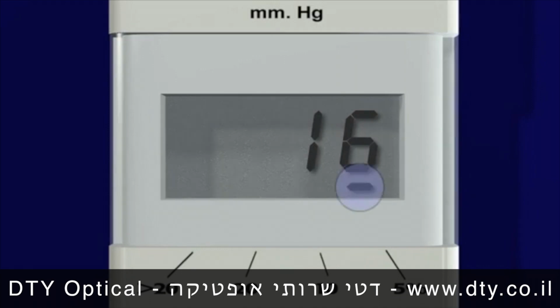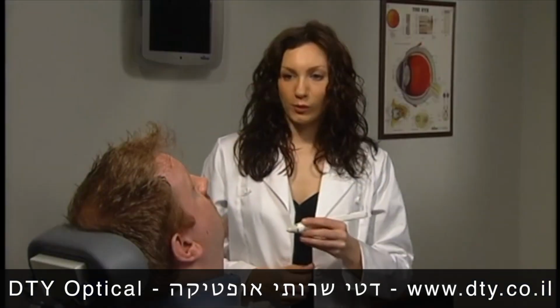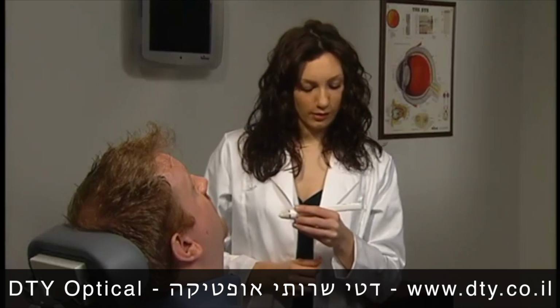Notice also the horizontal bar at the bottom of the LCD. This bar corresponds directly to the deviation index numbers. If the bar is situated at the far right of the screen, that means a deviation index of 5%. And if it's to the far left of the screen, that means a deviation of greater than 20%. Remember, the lower the number, the more reliable the reading. If you're satisfied with the results, the test is complete.